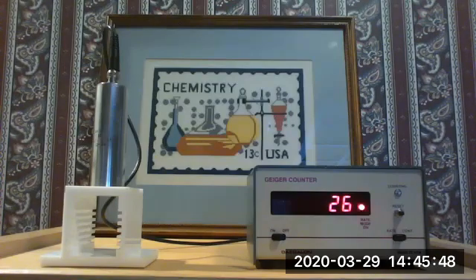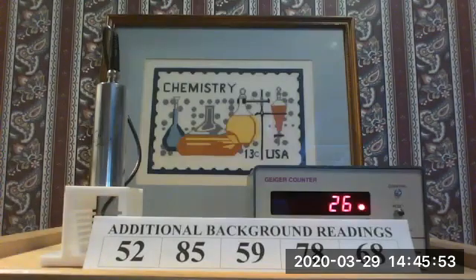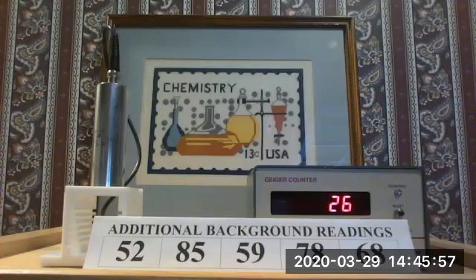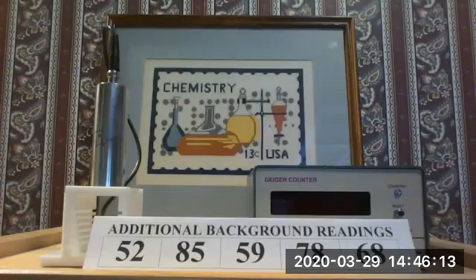All right, so in the interest of time, here are five additional background readings. So you'd want at least a total of 10 to get a good average background reading. So you can go ahead and write those down so that you've got 10 total readings for your background.